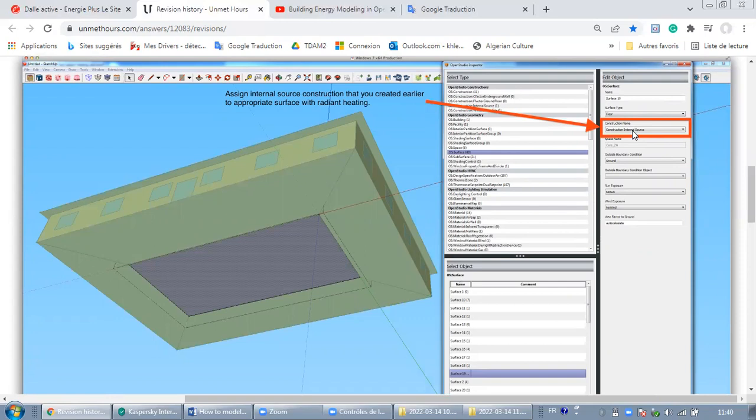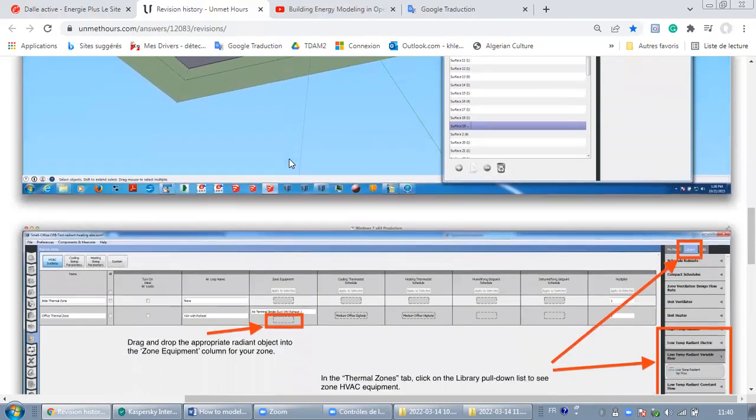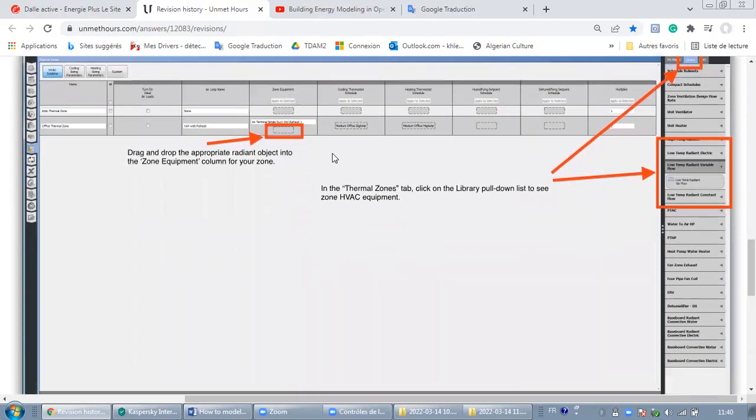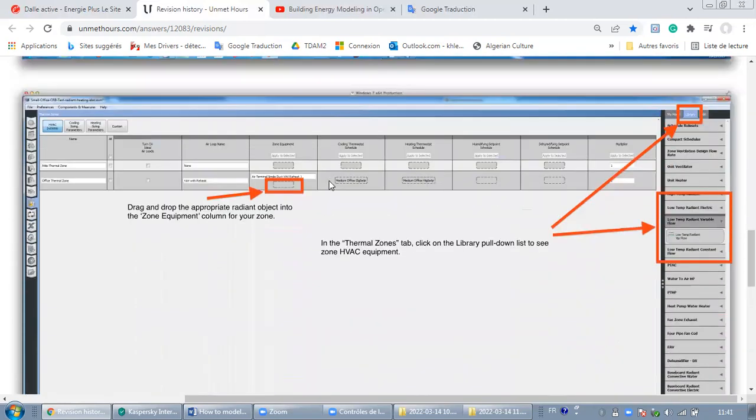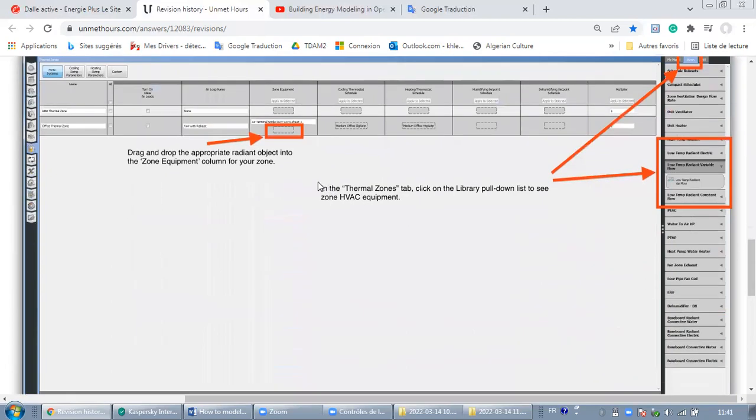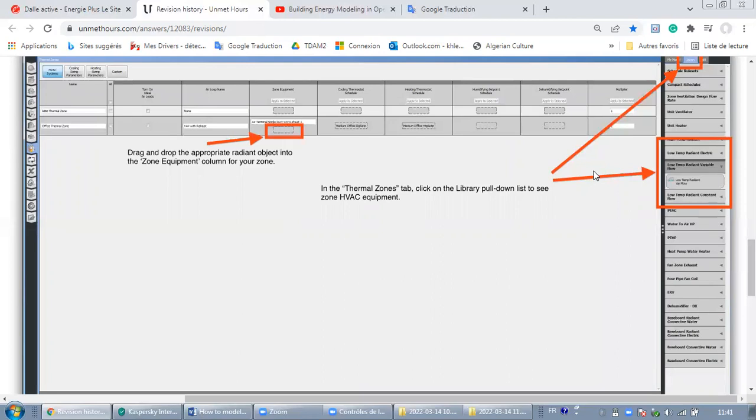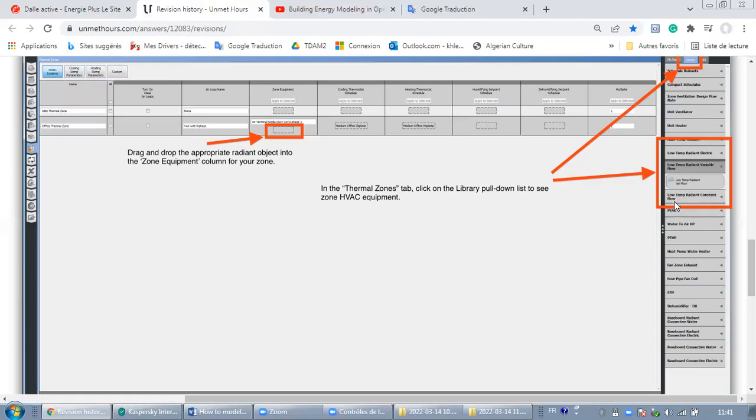Let's go to the third step. The third step: you may come back to your OpenStudio in the thermal zones tab. As you can see here, click on the library pull-down list to see zone HVAC equipment. In this step, you are going to add a new zone equipment right here. So from your library, drag and drop the appropriate radiant object into the zone equipment column for your zone. As you can see here, we find many radiant systems: low temperature radiant variable flow, low temperature radiant constant flow. So choose the right and appropriate radiant object and add it to your zone equipment.